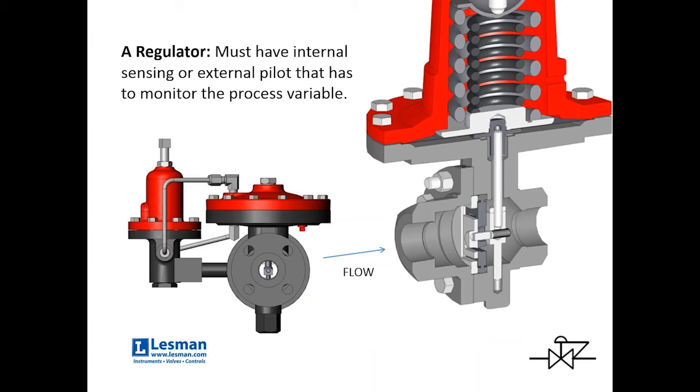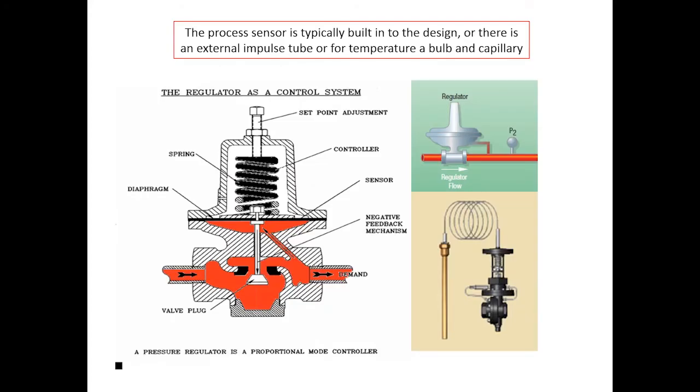So, a self-contained regulator, mechanical, no controller, no field device, has to get input from the process. And it either happens internally or sometimes there is an external pilot that will have access to the process. So, in this particular slide, it's a cutaway of a classic pressure regulator and if you can see the video here, the red represents where the process fluid is allowed to go. And you'll notice internally over to the right, there's a 45 degree path that allows the downstream pressure to interact with the diaphragm in the regulator. So, that little slice of pie there is how we're picking up the process variable.